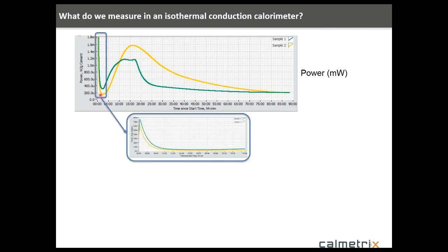I've blown up the initial portion of the curve with this instrument. Anytime you add a sample, drop a sample into the calorimeter, based on the mass and the heat capacity of the sample, you can have long equilibration times for the sample to come into precise temperature equilibration with the system. So as a result, there is heat flow generated just through this equilibration process, and that might take 2-3 hours depending on the sample.